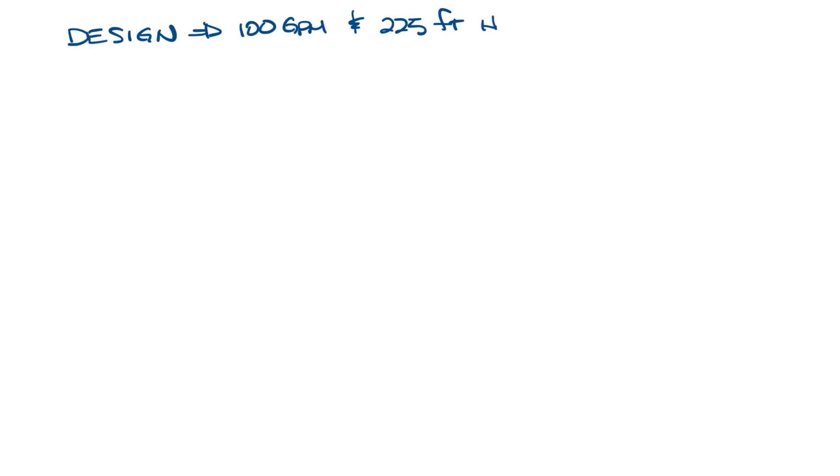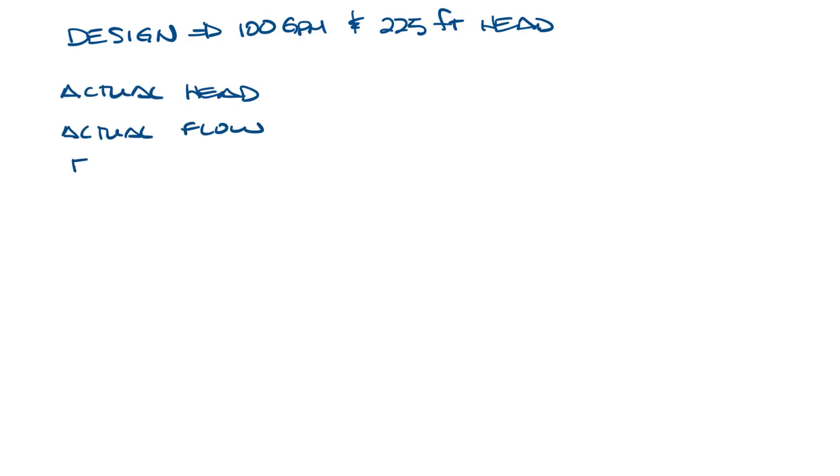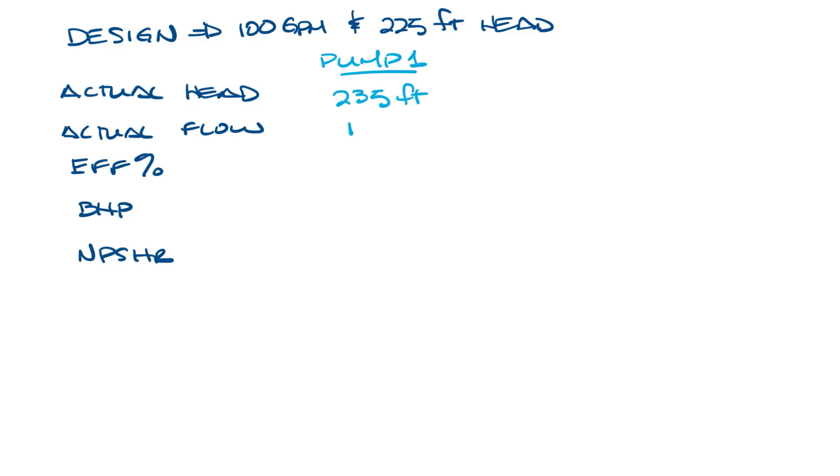First, we'll start with our design is 100 GPM and 225 feet ahead, and then we'll put the actual head, actual flow, efficiency percentage, brake horsepower, and NPSHR of the two pumps that we just looked at. So that's 235 feet, 126 GPM, 74% efficient, 10.10 brake horsepower, and 6.26 feet of head.